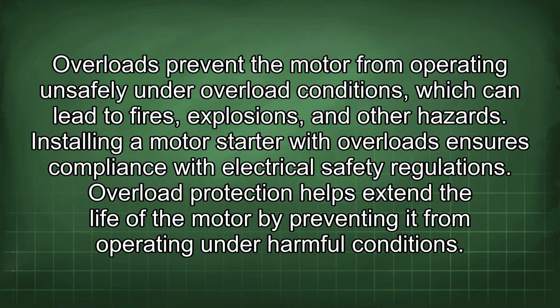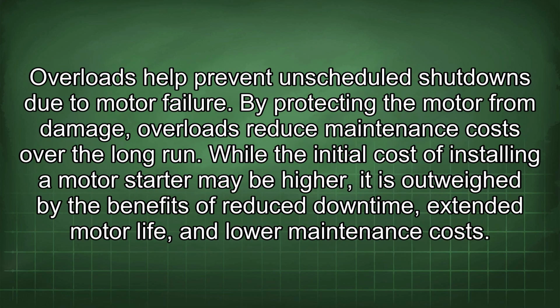Installing a motor starter with overloads ensures compliance with electrical safety regulations. Overload protection helps extend the life of the motor by preventing it from operating under harmful conditions. Overloads help prevent unscheduled shutdowns due to motor failure. By protecting the motor from damage, overloads reduce maintenance costs over the long run. While the initial cost of installing a motor starter may be higher, it is outweighed by the benefits of reduced downtime, extended motor life, and lower maintenance costs.